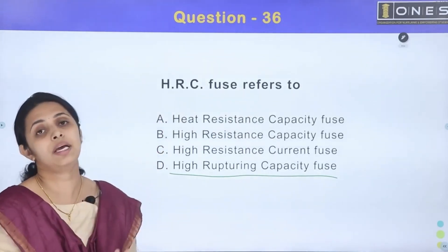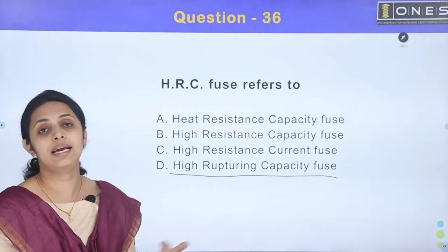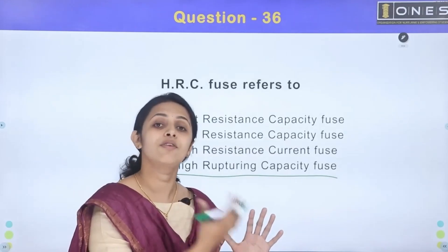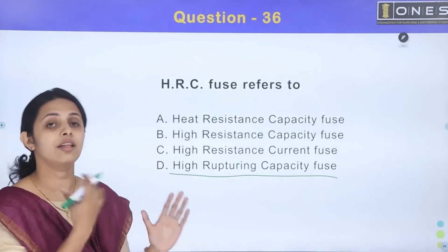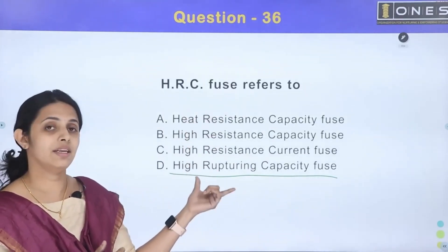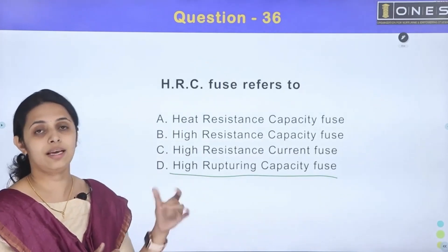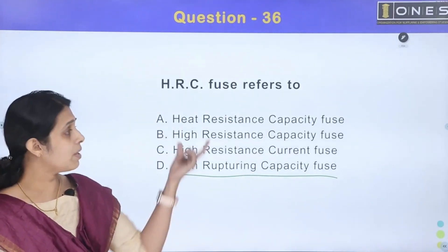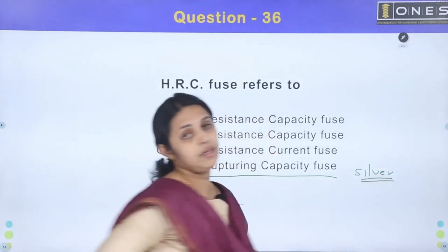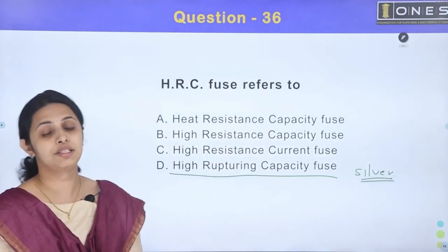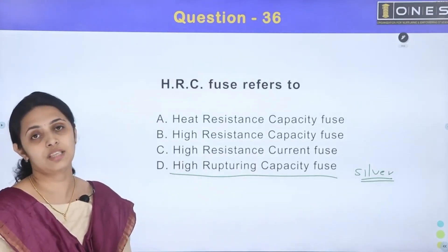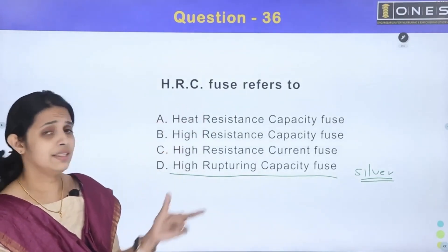The HRC Fuse can withstand fault current; if the fault current is not high enough, the fuse will not melt. We use a metal element inside the HRC Fuse — specifically a silver fusing element. With high current passing, the silver will burn and melt, protecting the circuit.